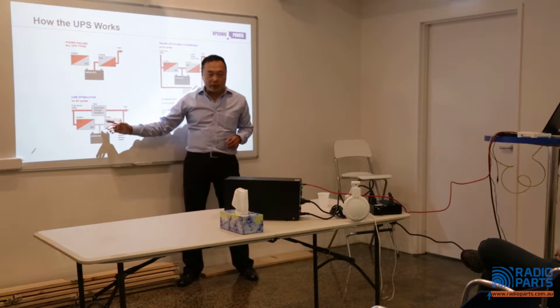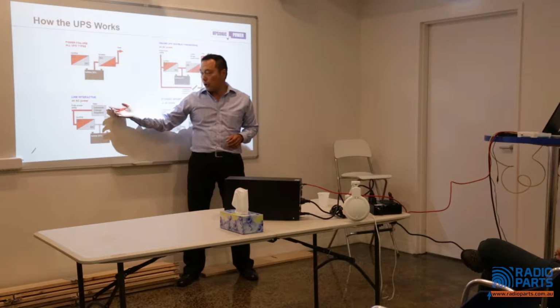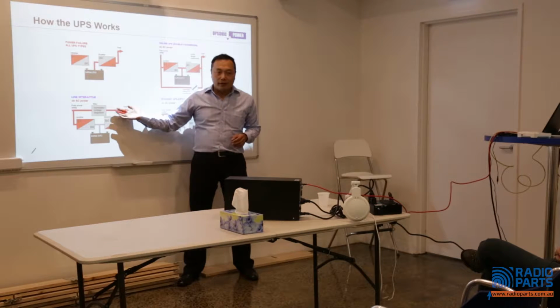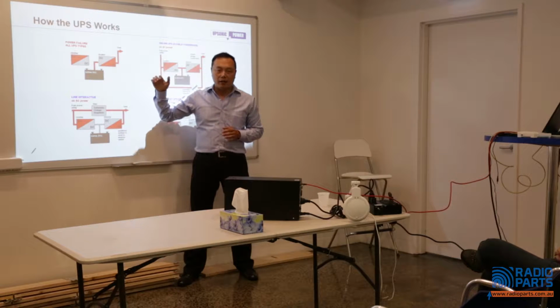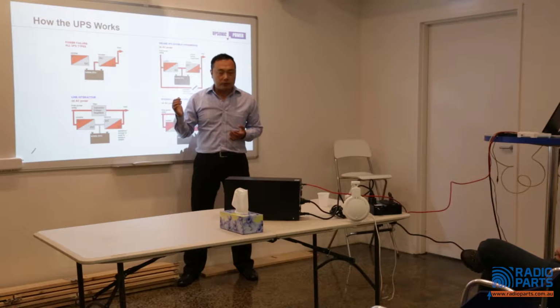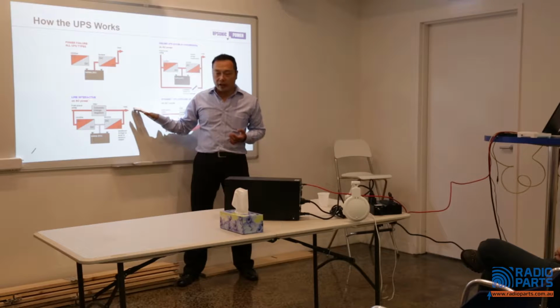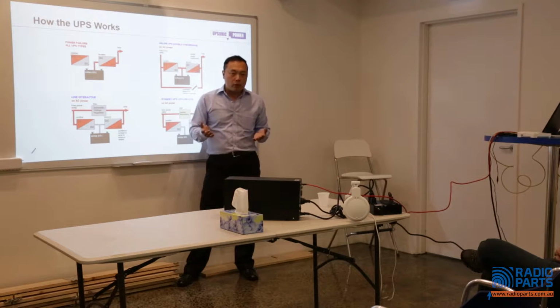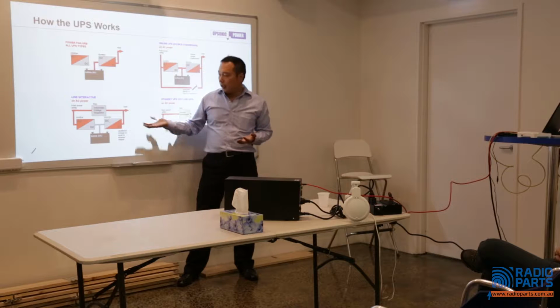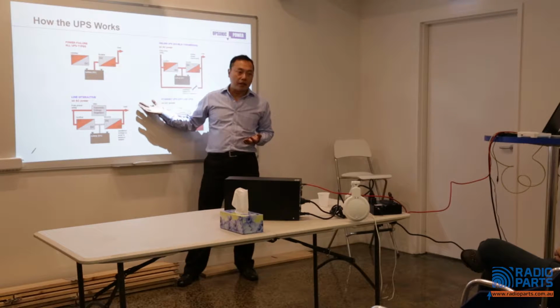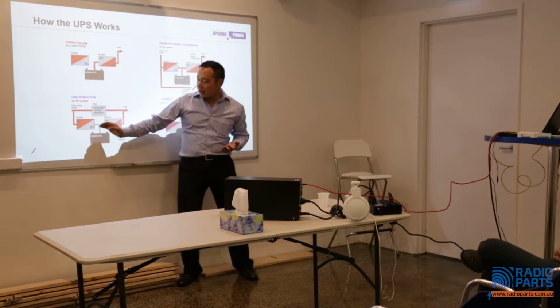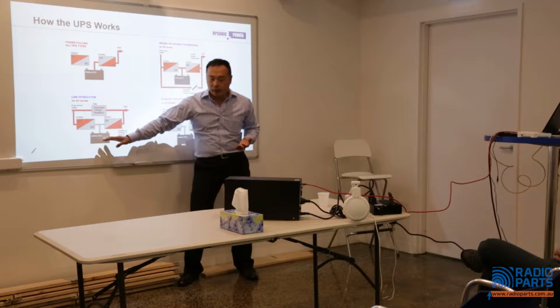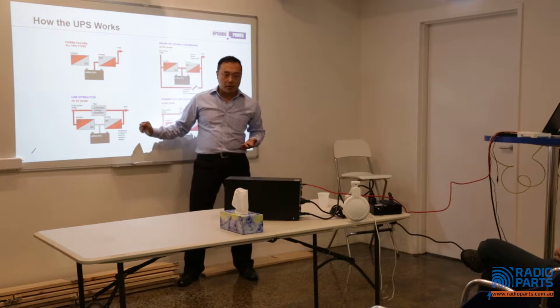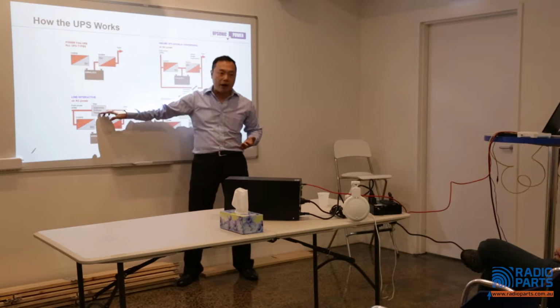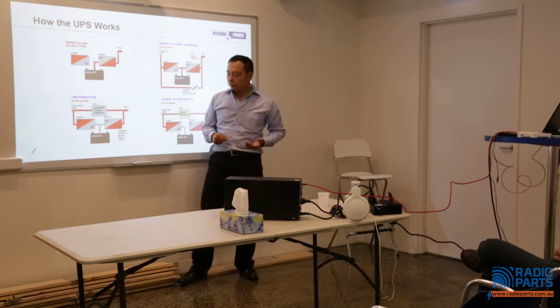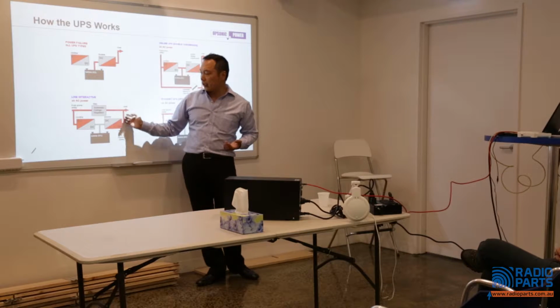This automatic voltage regulator automatically regulates the voltage. When the voltage is too high, say 270 volts, it will buck it down to 230. If it's too low, say 170 volts, it will boost it to 230. At the same time, it charges the battery, but the inverter is not working. All the power goes through this AVR, buck and boost. So we got this line-interactive design.